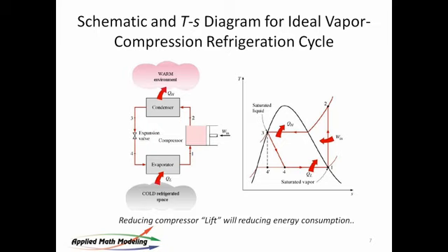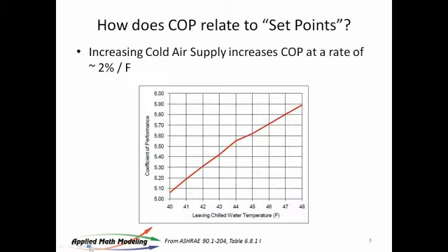They call that delta P, that pressure, lift. So reducing the compressor lift reduces the energy consumption. And there's a couple of ways to do it. One of them is drop the temperature of the condenser down. The water entering the chiller, if you can get it down, that'll do it. Or if you can get number 4 up, which is supply air temperature, and we'll talk about both of those.